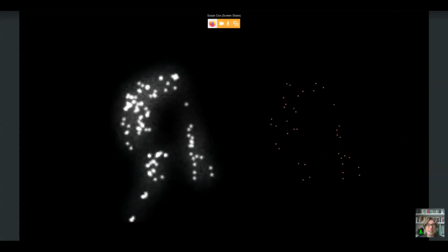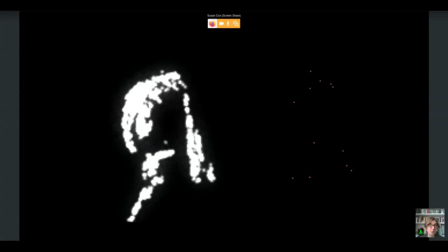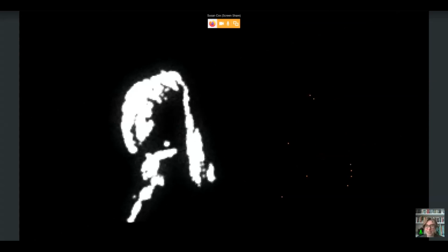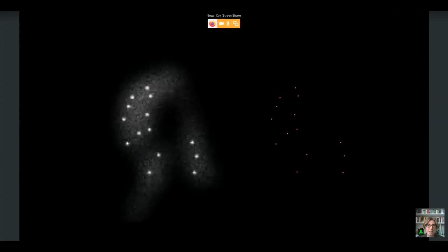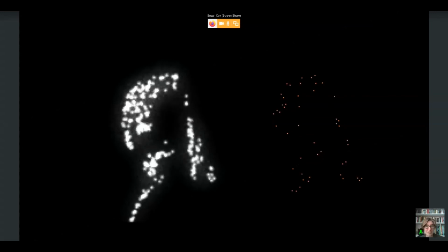And you can see as I increase the activation density for a while, I get more fluorophores being localized on the right. I'm filtering them out after a while so that we can just see how many are being localized for a given activation density. It increases for a while, but then as I increase the activation density further, it decreases again because fluorophores are overlapping and I'm not able to image them successfully.